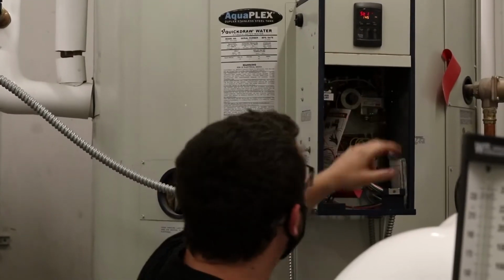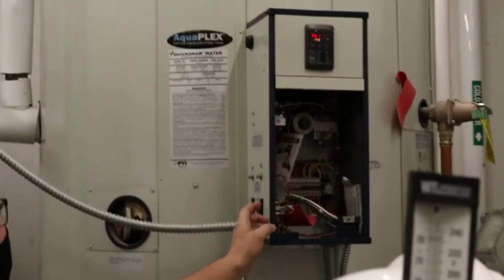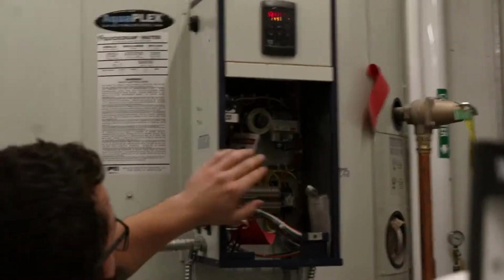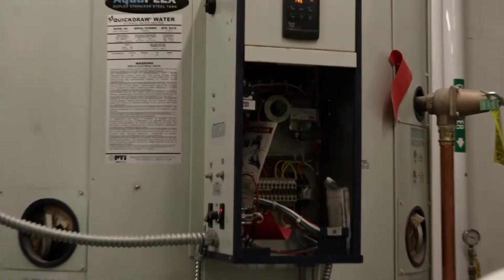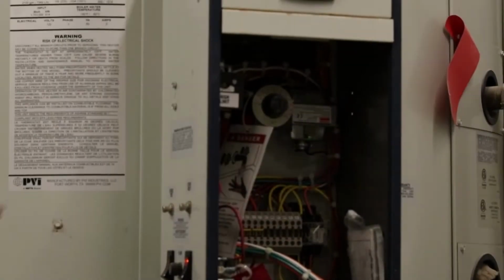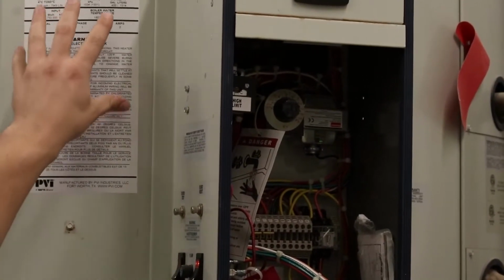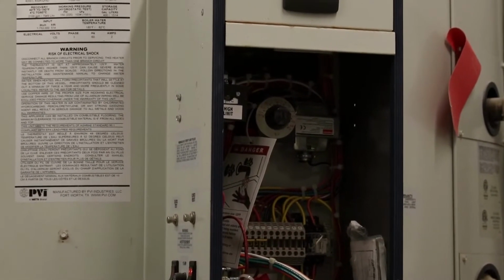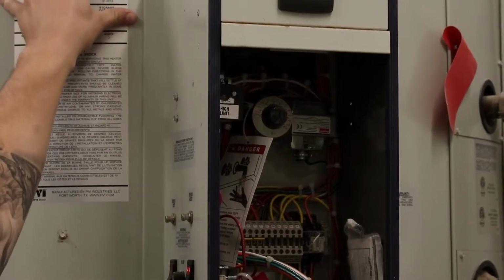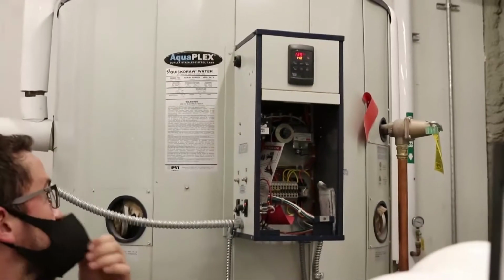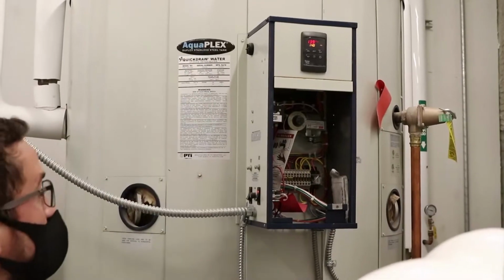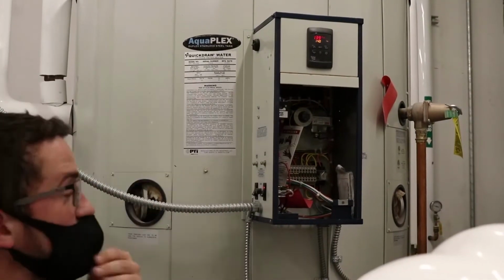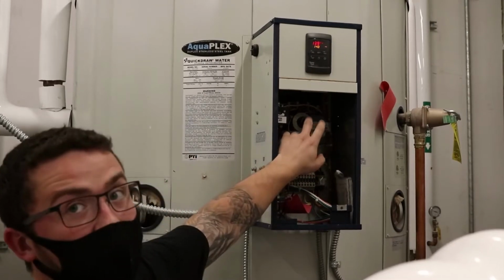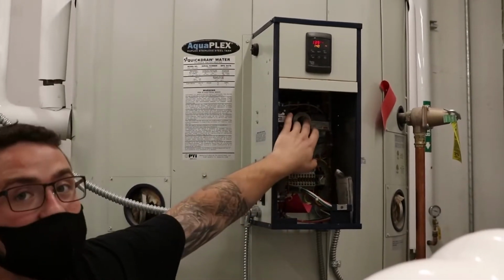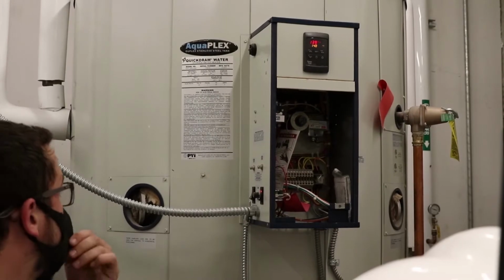In here you have a secondary temperature controller. They call it the upper operating control. This is meant to be set 10 degrees higher than the set point, and it is connected to a probe at a higher point in the tank. It is there simply to make sure that as the water heater is heating water where the heat exchanger is, you are not creating water that is too hot up top. So it acts as an automatic resetting high limit. It will limit the temperature at the top of the tank to whatever temperature you set the dial to. And again, that should be 10 degrees higher than the operating set point.